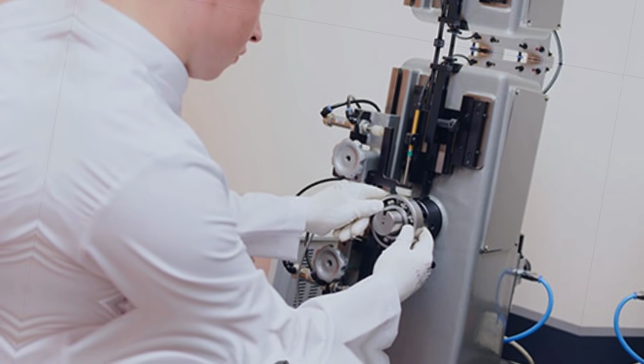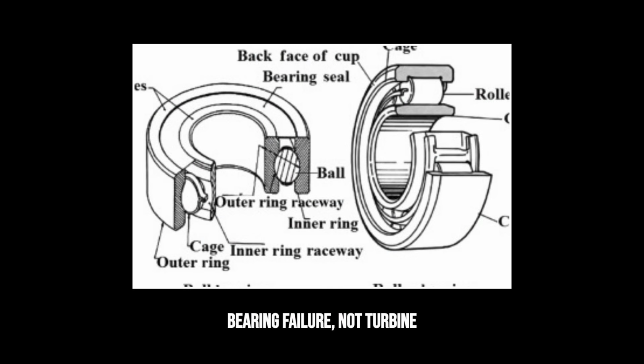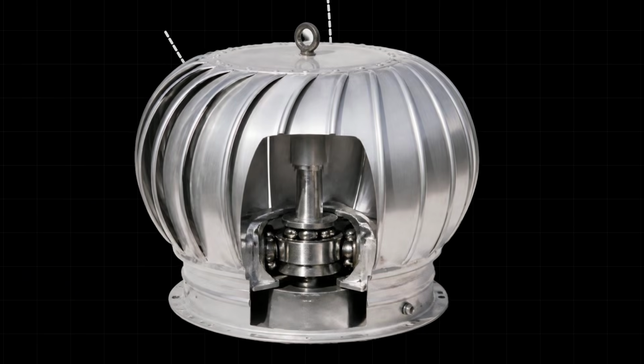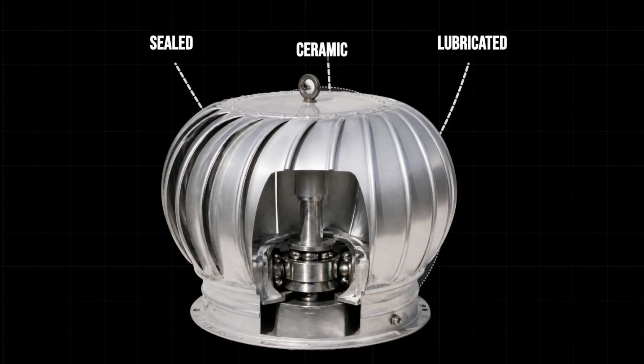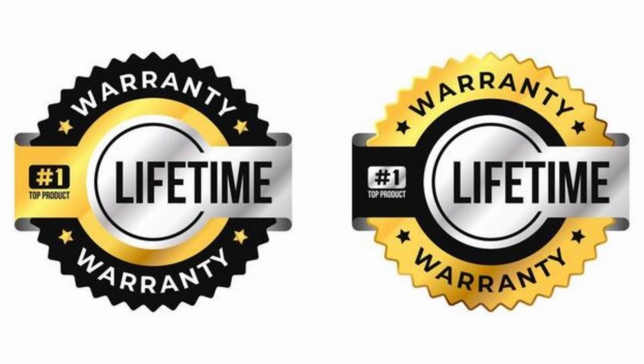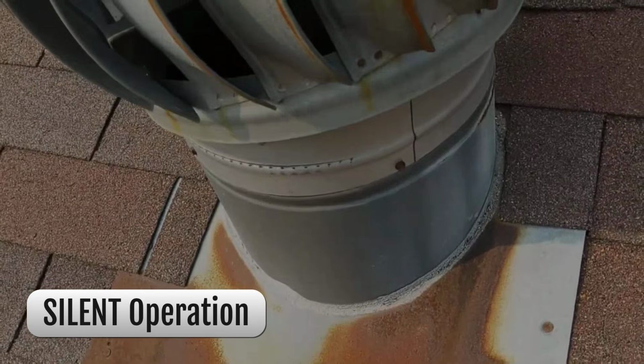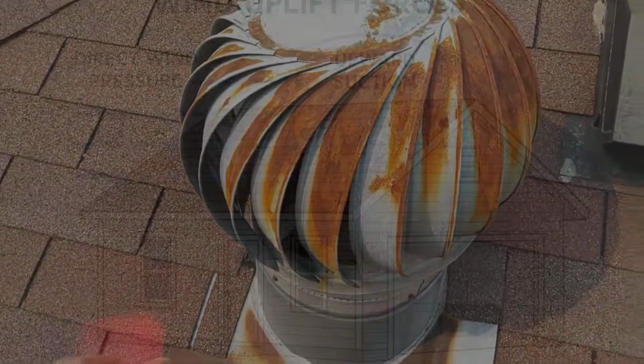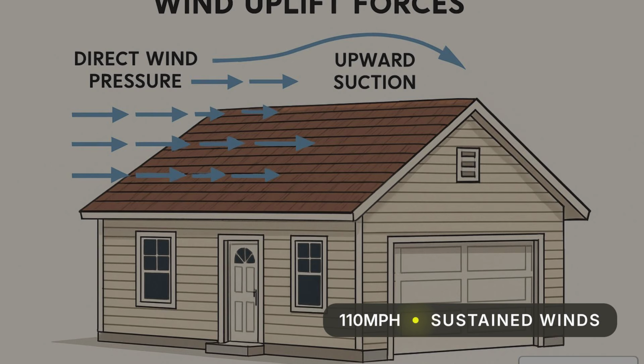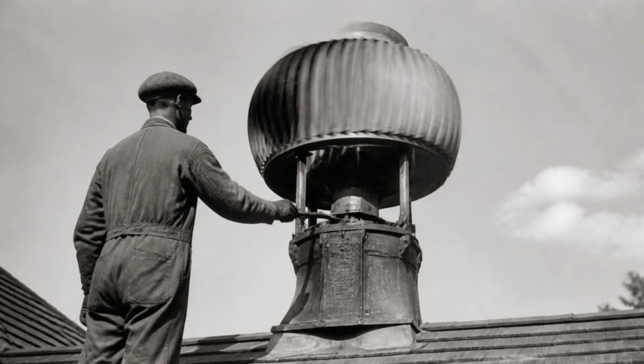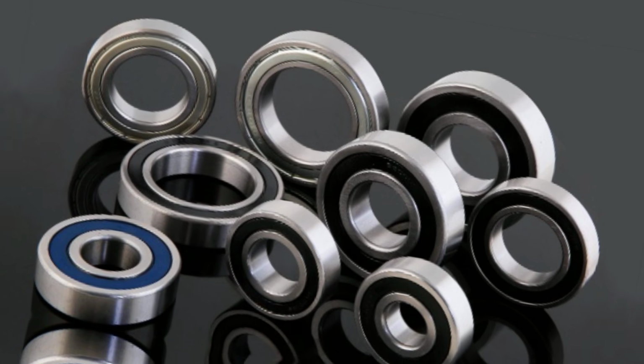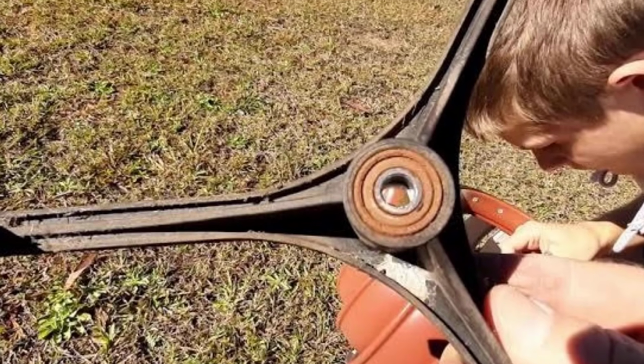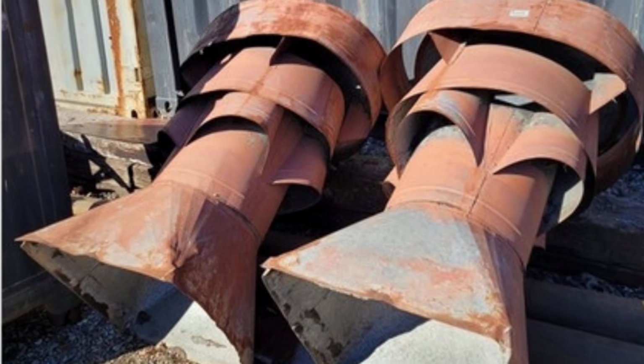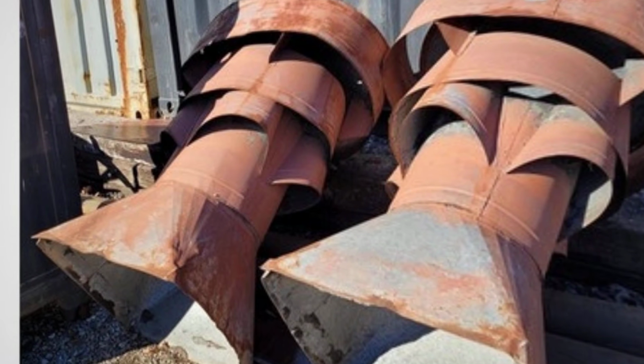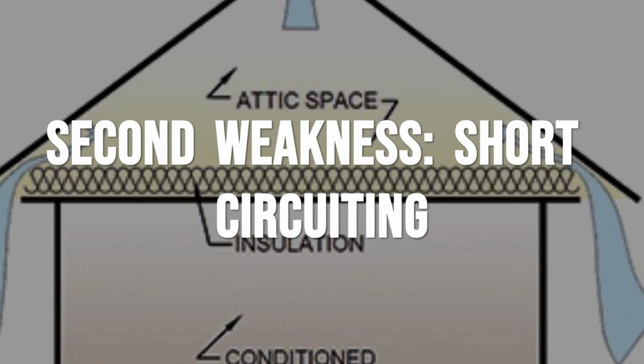What engineers discovered was that the bearing itself was the problem, not the concept. Modern turbine ventilators now use permanently sealed, permanently lubricated bearings rated for the full life of the unit. Independent stress testing has verified units maintaining silent operation after exposure to sustained winds exceeding 110 miles per hour. The noise problem, the single most common complaint against the original design, no longer exists in quality modern units. If you have avoided turbine ventilators because of noise, you are making a purchasing decision based on hardware that is no longer being sold.